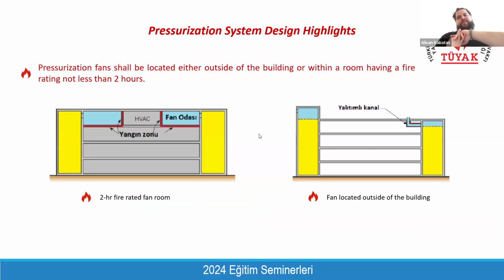And also, if you have a pressurization system, the pressurization system is preventing smoke from entering the fire escape stair by giving fresh air into the stairwells. That's why the location of the pressurization fan is very important. You either need to locate it at the top of the stairwell, meaning outside of the building, or you can locate the fans within the building. But when you locate the fans within the building, the room where the fans are located will be considered a part of the fire escape stair. It means it should be 2 hour fire rated and separated from other areas.